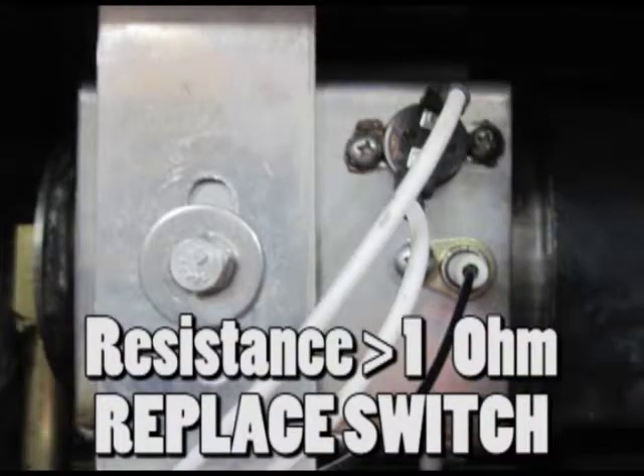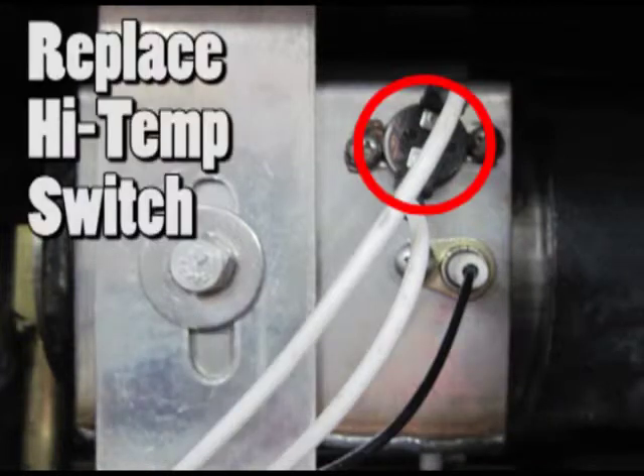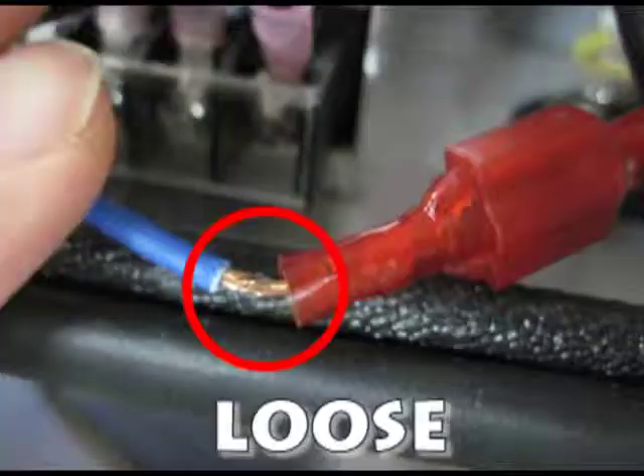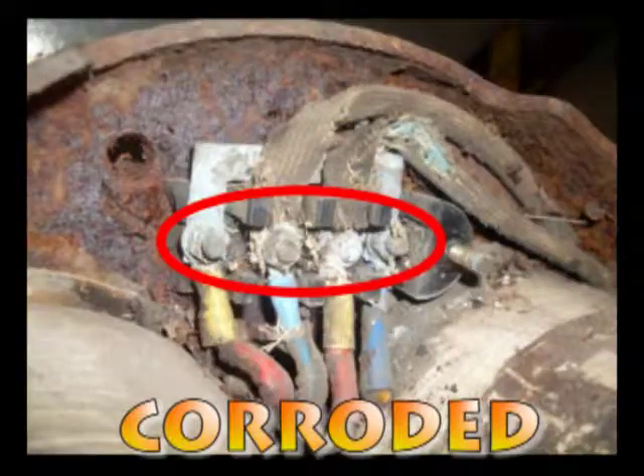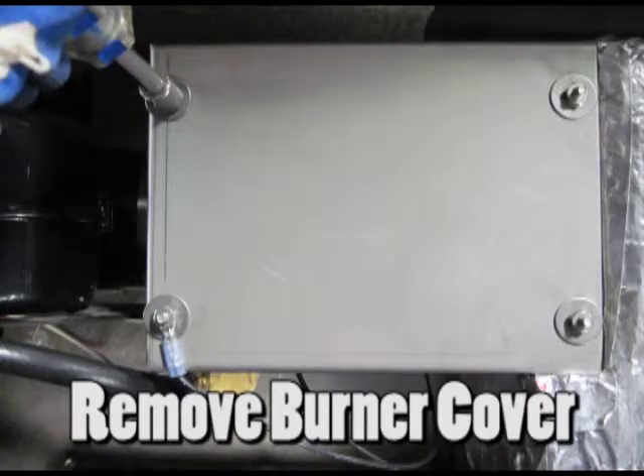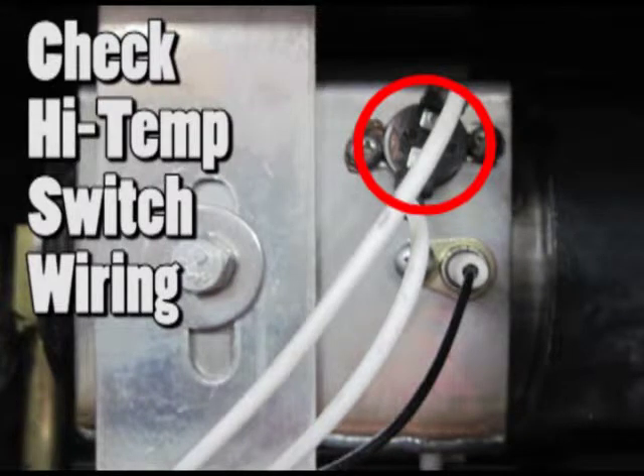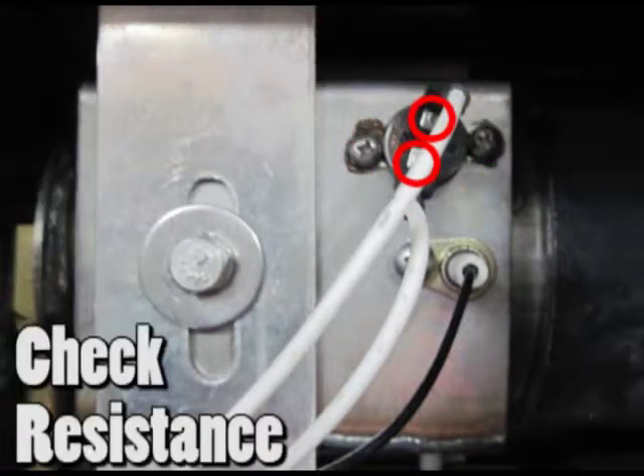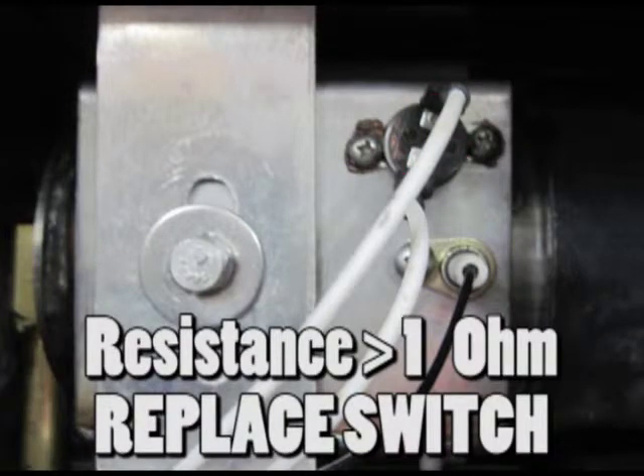If this measurement is anything greater than 1 ohm, the high temperature safety switch needs to be replaced, or the wiring associated with this switch is loose, damaged, or corroded. Remove the cover to the combustion chamber and check the wiring for the high temperature safety switch. Check resistance across the high temperature switch. Anything more than 1 ohm requires a new switch.